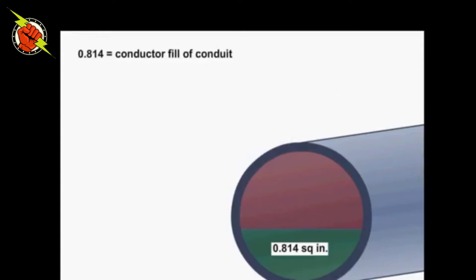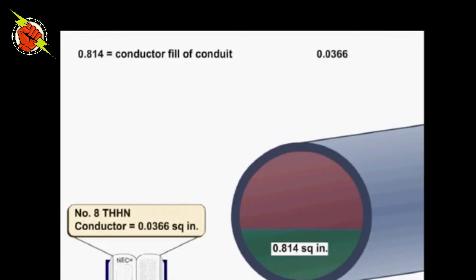Step 2. Determine the cross-sectional area of the existing conductors. Per Table 5 in the NEC, the cross-sectional area of a number 8 THHN conductor equals 0.0366 square inches.